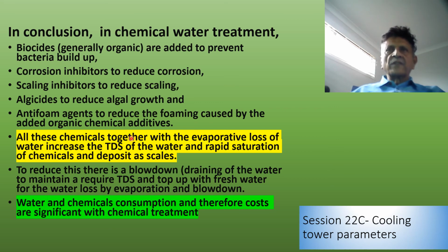Of course, for example, if you drain 50% of the tank and add 50% top-up water, what you would be doing is reducing the TDS by half, assuming the incoming TDS of the water is minuscule compared to the actual TDS of the saturated solution.